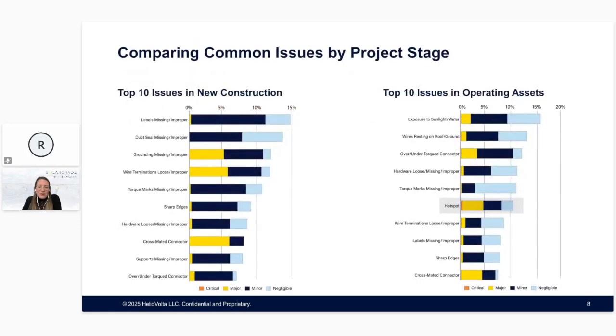Let's look more closely at the most common issues overall in new construction inspections versus operating asset inspections, at every level of risk severity. There's a fair bit of overlap: issues with improper connectors, wire management, wire terminations, labeling, and hardware appear on both lists. But hotspots, the 6th most common issue in operating assets, don't even make the top 10 for new construction. We know thermal issues are the top cause of downtime, yet nothing temperature related hits the list for new construction.